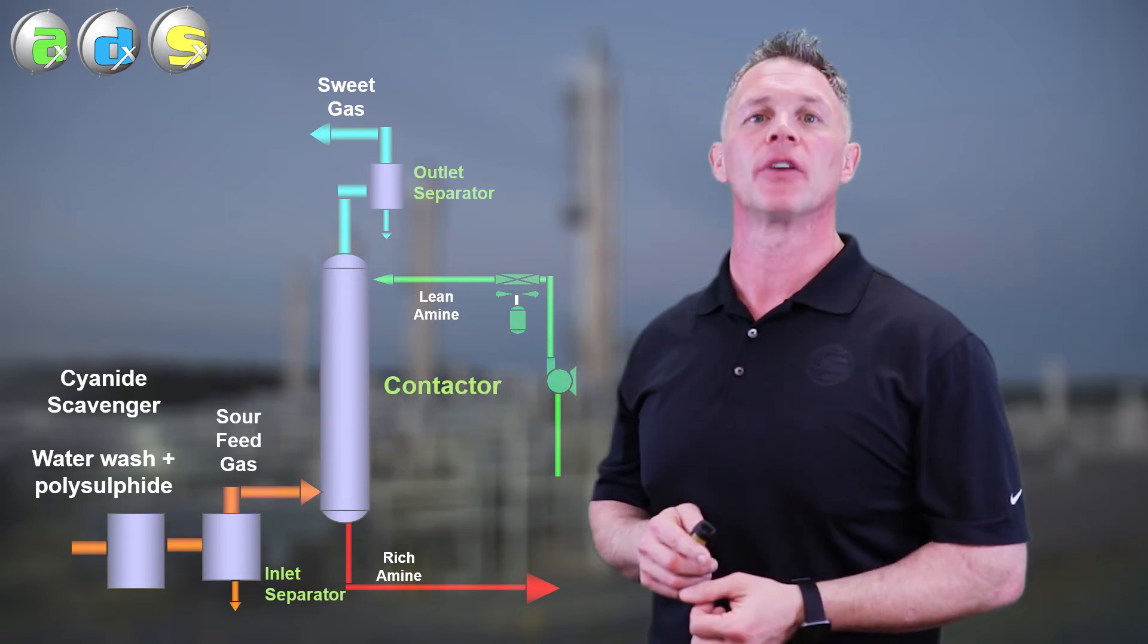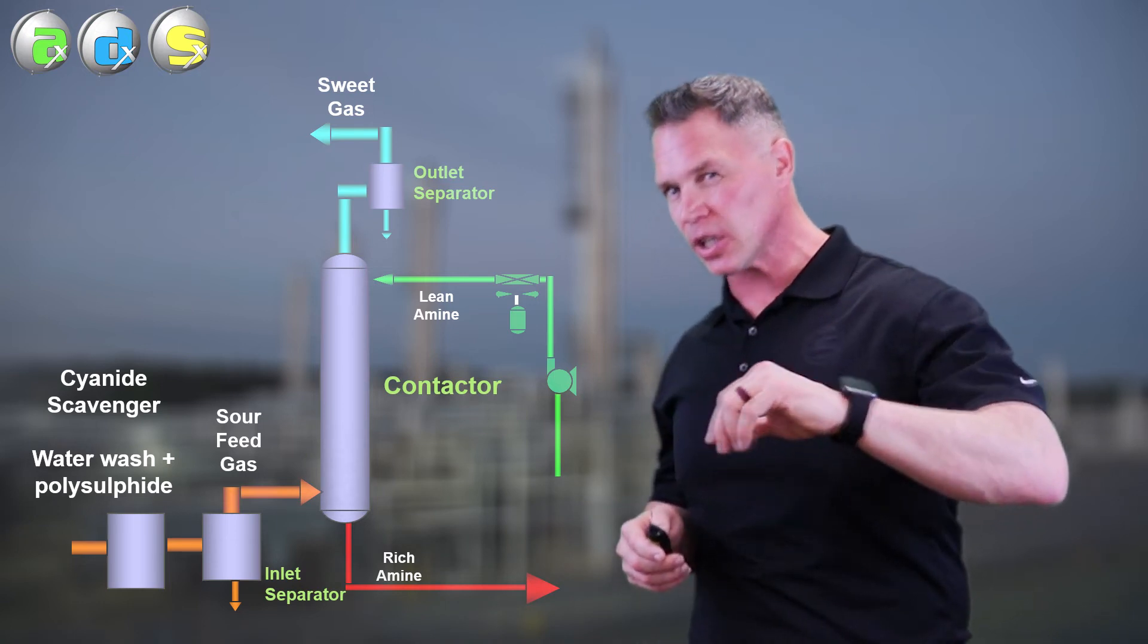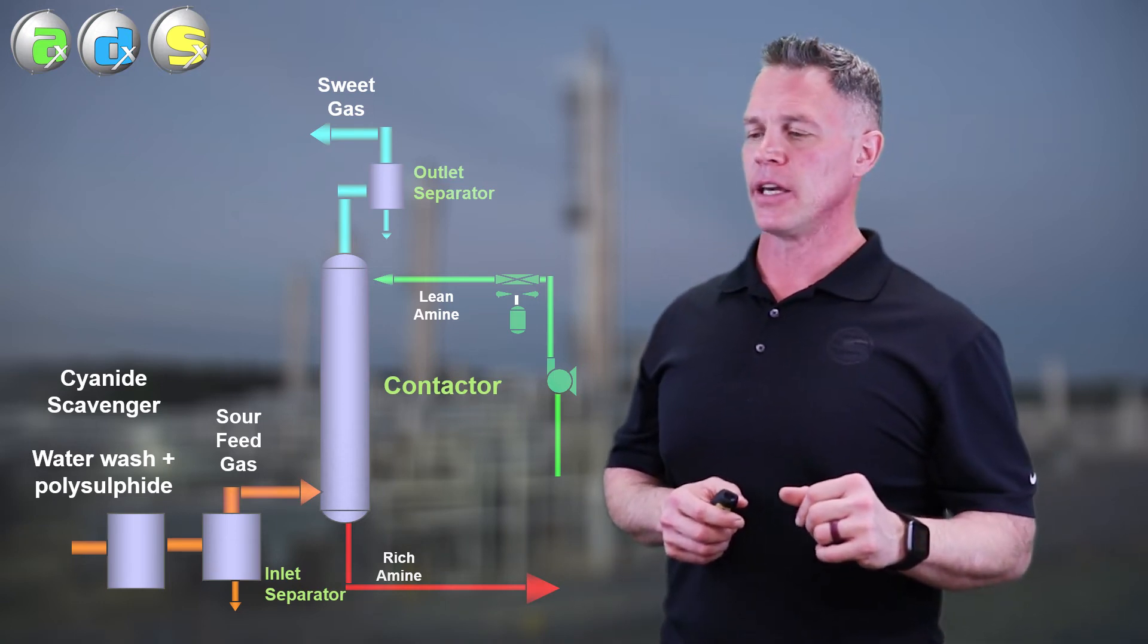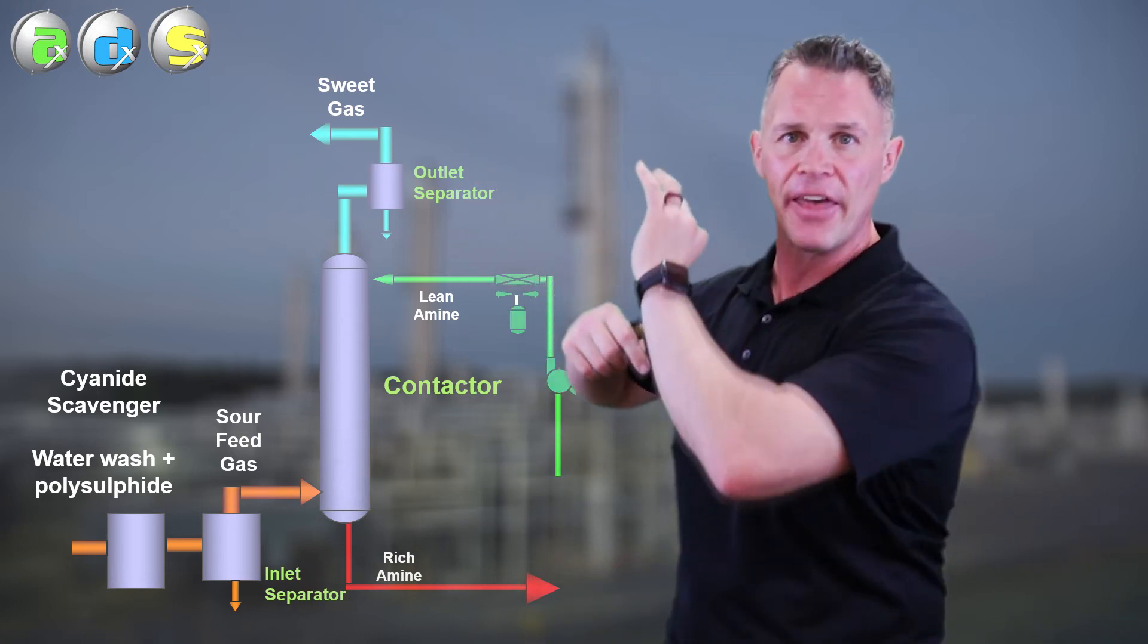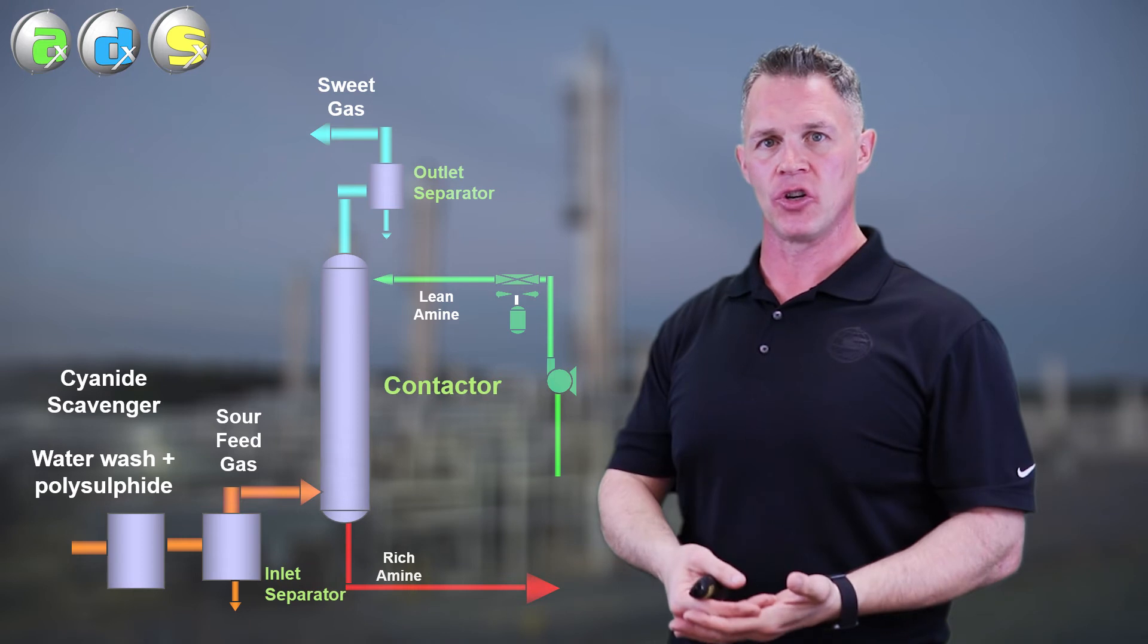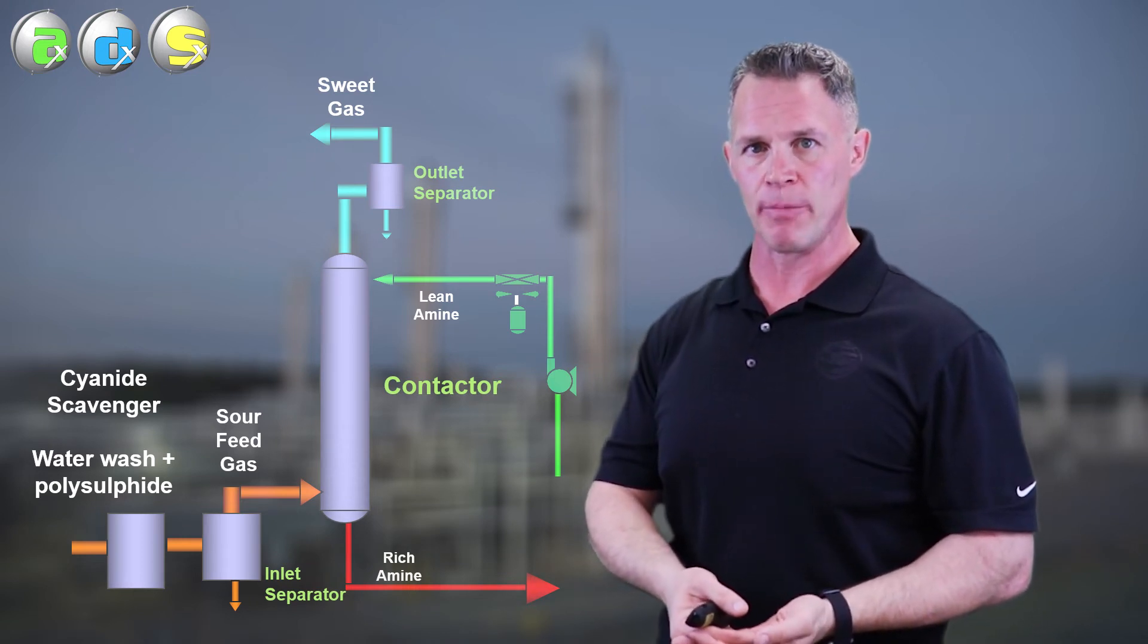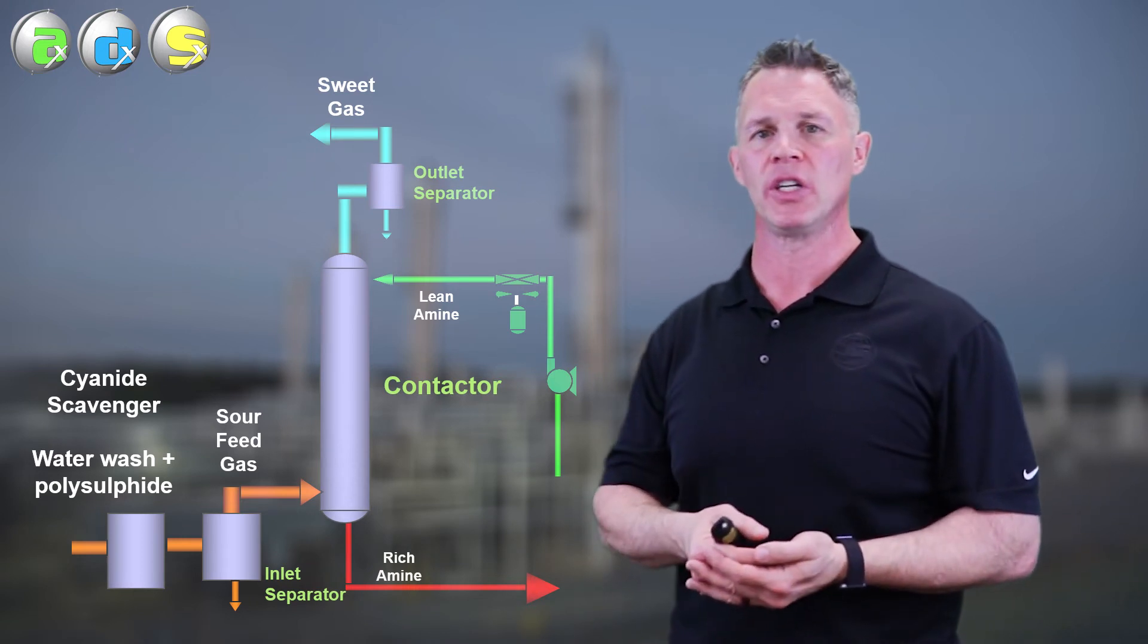Basically the most common one is a water wash. You bubble the gas through a water wash first and the water wash contains a cyanide scavenger, such as a polysulfide, ammonium polysulfide, the most common one we've seen in the field.